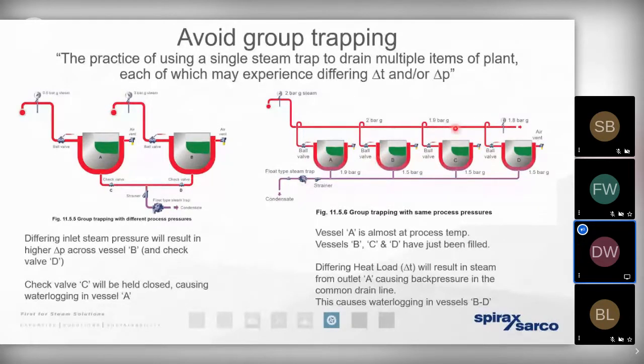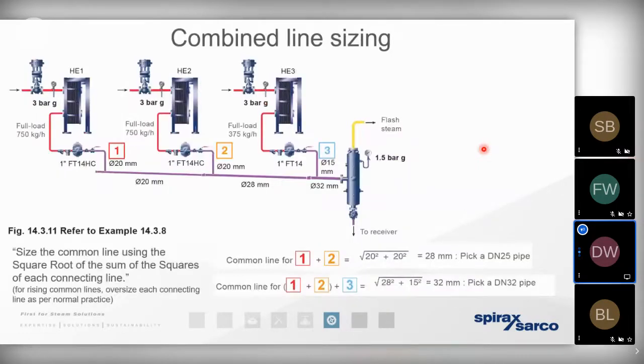And that back pressure can prevent the condensate from leaving the system or the process, resulting in a slowing down of temperature, but also resulting in that erosion, corrosion and water hammer that we've spoken about. So we do encourage you to have an individual trap dedicated to each process. However, that's not to say that the condensate pipework can't come together and converge, so we're removing that condensate in a group line. All we need to do is allow for the pipework to step up incrementally in accordance with the increase in mass flow rate of liquid condensate, but also the increase in volume of flash steam that is present.